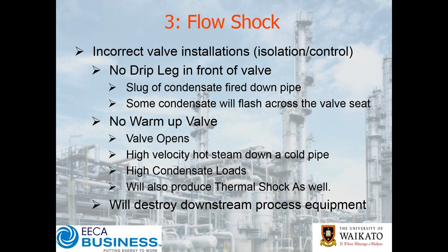With that explosion we get a pressure pulse, which is manifest in the form of water hammer — this is our flow shock. It's when that condensate flashes across your valve seat — that's going to erode the valve seat. This is why a lot of places pay a credible amount of money to re-kit valves every year, because they know the control valves start to wear away at the valve seat from condensate flashing across the control valve.